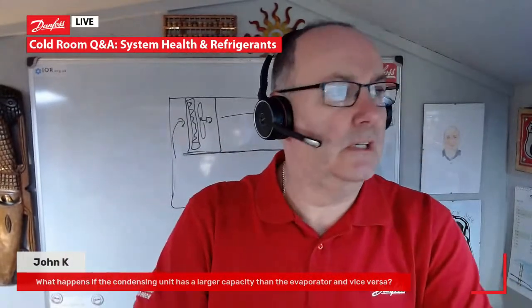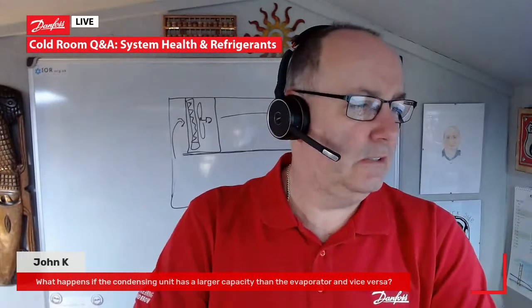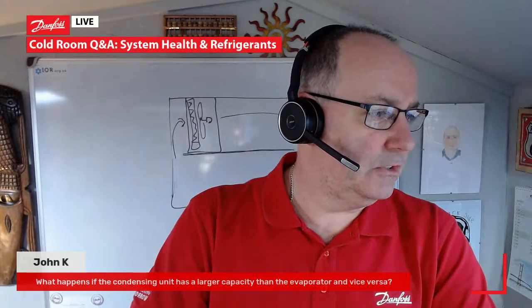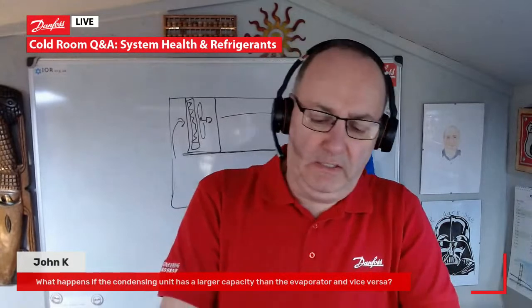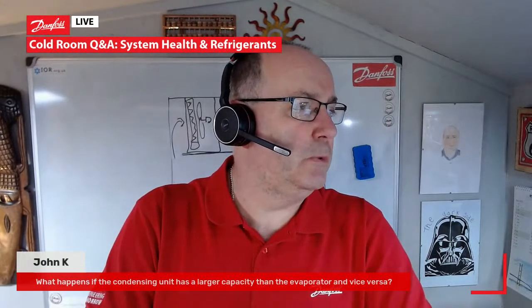Okay, so a question that's come in from John. What happens if the condensing unit has a larger capacity than the evaporator and vice versa? That's a good topic, actually. Let me just put another slide up a second. Basically, one of the webinars that we did was the selection match between condensing unit and evaporator. And one of the topics that I get asked a lot when I'm on site is, what defines the evaporating temperature of a system? Is it the evaporator and the condensing unit? Is it my suction pressure? How does it define itself? And basically, when we start looking at system match, I'll just put this little picture up a second, and then we'll go on to look at some more. So let me just swap the screens around a second. Okay, so let's put that up on the screen.